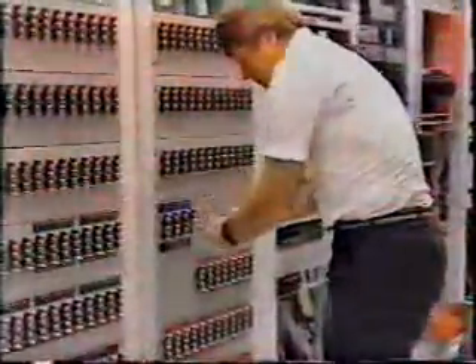Finally, when testing of secondary wiring is completed, the permanent ground should be reconnected. Remember, this wiring is usually grounded at one single point only. Make sure that this is so. The secondary wiring can now be energized when required.